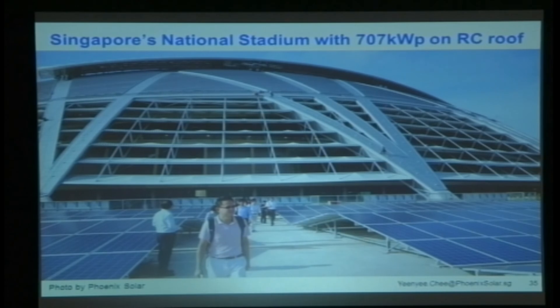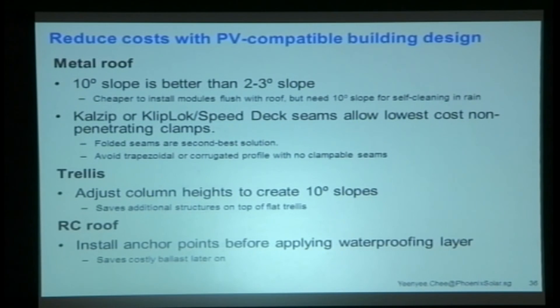This is the Singapore Sports Hub — the new national stadium — and the PV systems that have gone in there. To summarize: reduce costs by working with a 10-degree roof slope, as it's cheaper to install modules flush than to erect additional structures. Use Kalzip or KlipLok roofs with clamping — very easy and fast. Avoid trapezoidal profiles where you have to drill. For a trellis, it's very cost-effective to just increase the slope a little bit when building. And for RC roofs, put the anchor bolts in before waterproofing so you avoid the whole waterproofing complication later.